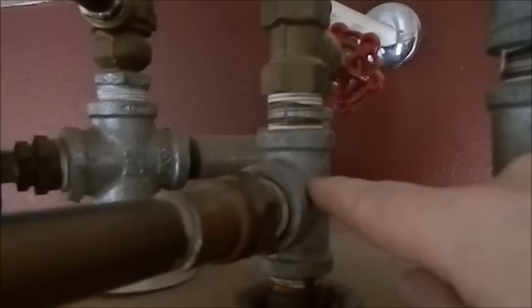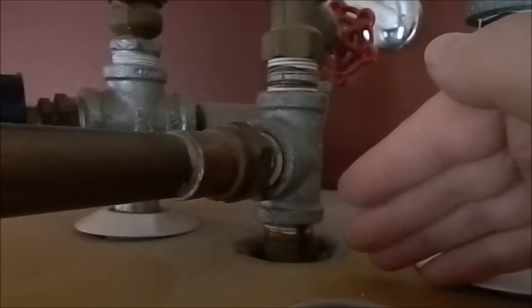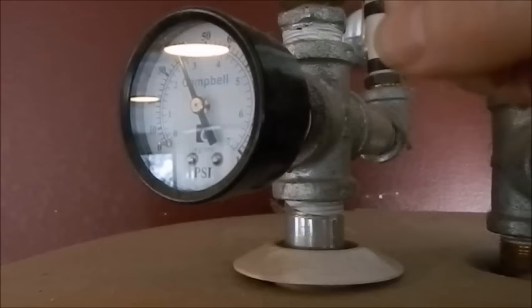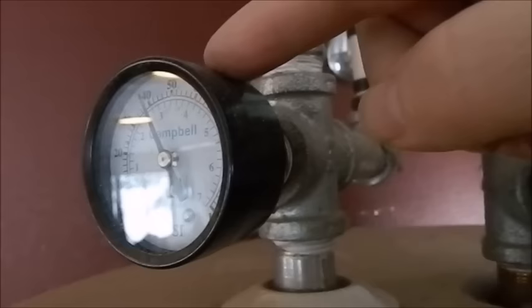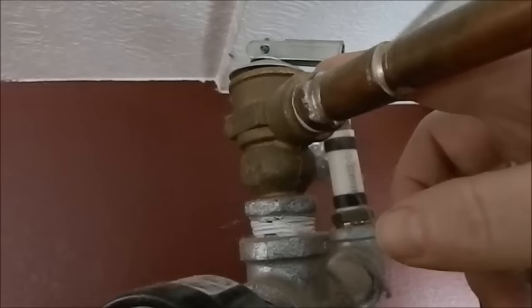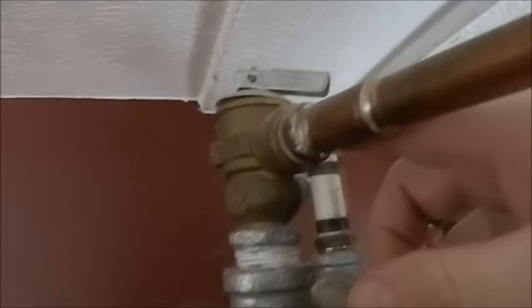The hot water comes off the pop top here, goes up, and then travels down to the center — this is where the old temperature and pressure (T&P) valve used to be. The T&P valve is not gone; I just moved it to a different spot. You need to have a temperature and pressure valve in the system. The domestic hot water pipe comes right off here. I also have a pressure gauge to monitor system pressure. The temperature and pressure valve I installed blows at about 150 to 175 degrees, which is really important.